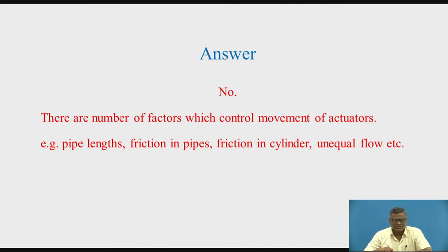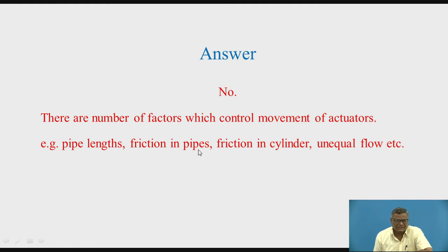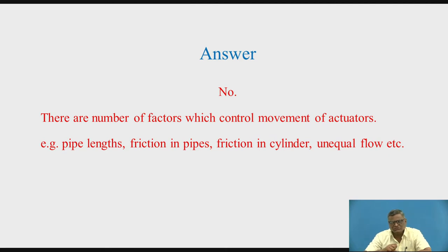The answer is no. There are a number of factors controlling the movement of the pistons. One is the pipe length — from the common pipe, one goes to the cap end of the first cylinder and another to the second, and the length matters. Friction between oil and the inner surface of the pipe matters. Friction between oil and the inner surface of the cylinders also matters, and unequal flow distribution means exactly 50/50 percent will not go to both cylinders. So one piston moves ahead and the second follows — these are not synchronized movements.